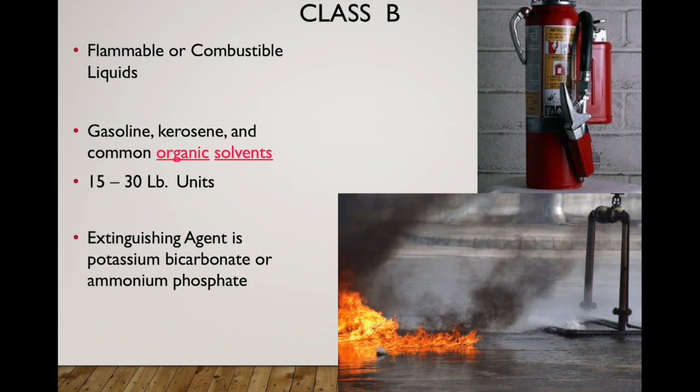But if we can do some simple processes such as diking or damming, so using our hand tools to move some dirt or soil or whatever else is around in that area, or maybe calling for some sand, we can contain that fuel fire and then easily put it out with our Class B dry chemical extinguishing agent. Or we also have the ability to use Class B firefighting foam in our hose lines.